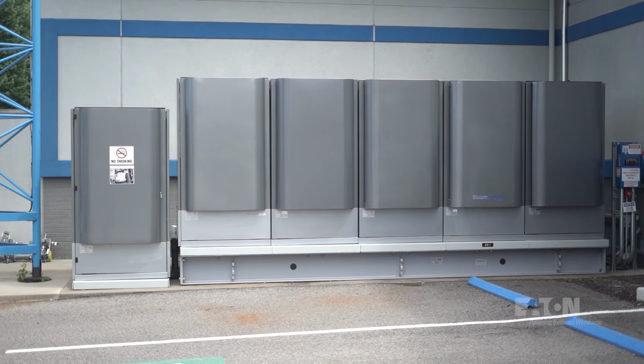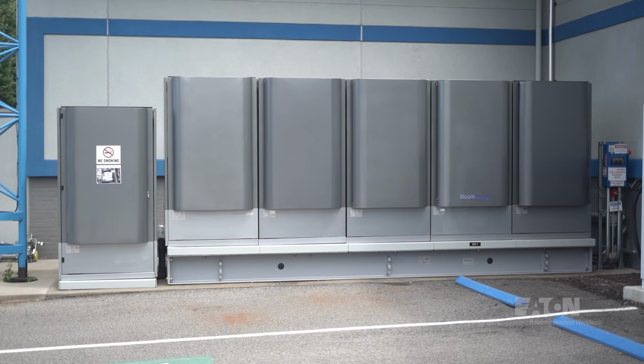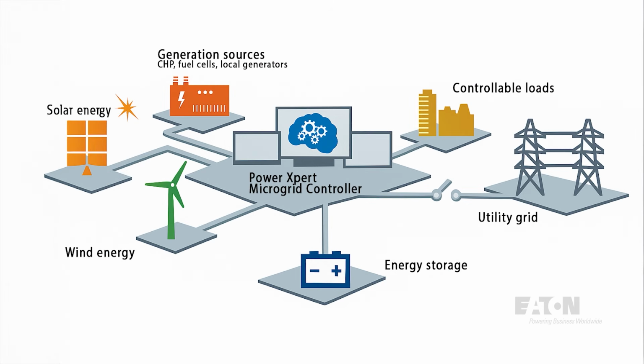While these systems provide backup or supplemental power, we recently added a new technology that offers something different: continuous clean energy, a Bloom Energy fuel cell to provide 50 kilowatts of power all day, every day. So when the sun isn't shining and the wind isn't blowing and the batteries aren't charged, we can still reduce our demand from the utility by 50 kilowatts with a very clean, reliable source of energy. In addition, this unit can also work in conjunction with our microgrid, or with downstream loads, we can use it as an islanded source of power.